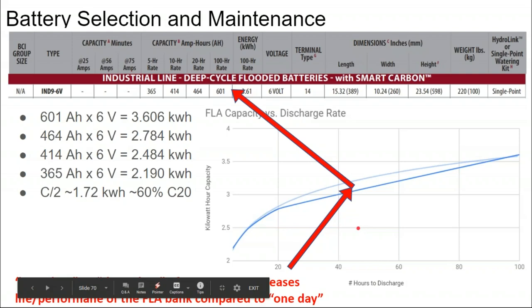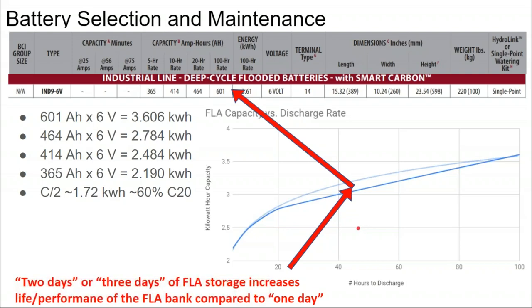So the short of it is a lead acid battery that's designed to meet the needs of an entire house for 2 hours and fully drain over 2 hours, that's not a good selection, because due to the rapid rate of discharge, that battery is going to have to store twice as much power as the equivalent lithium ion.